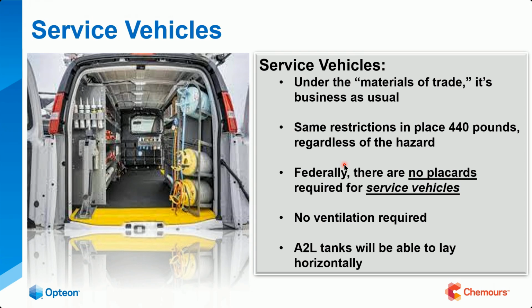So that's kind of a breath of fresh air that they didn't lower that for the A2L refrigerants. Now, federally, on the service vans, there are no placards required for service vehicles. No placards. And also, another myth buster: no ventilation required.